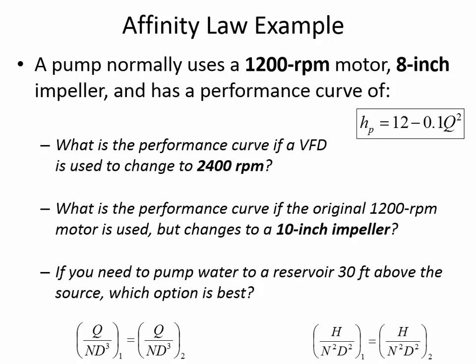And then we also rearrange this equation to give us H sub P1 is equal to 1200 squared divided by 2400 squared times H sub P2. So that is 0.25 H sub P2. So we know the relationship between Q1 and Q2 and H sub P1 and H sub P2. And we put that into the original expression for the pump curve that was given by the manufacturer.